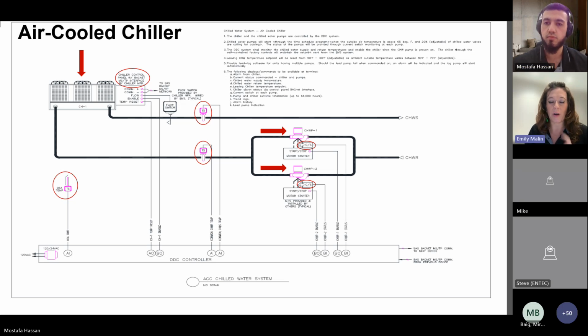I think also maybe what you're asking is using the functionality that's built into the pumps itself, right? Instead of wiring it into the control system itself, like Moose was saying. And I think the only disadvantage is if you can't tie in the features like Moose was talking about, like alarming, and it might also create more of a maintenance task. So then you might not be able to do slight changes or maintenance on your BAS system itself, if it doesn't integrate natively from those onboard pumps into your BAS system.